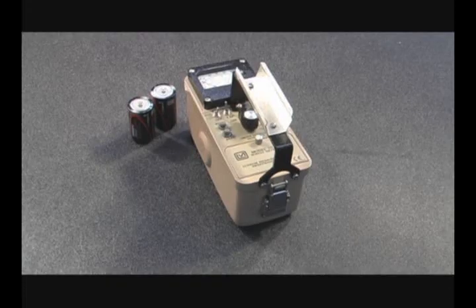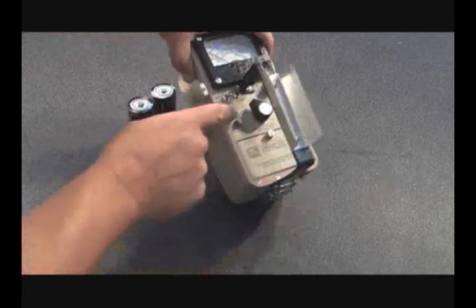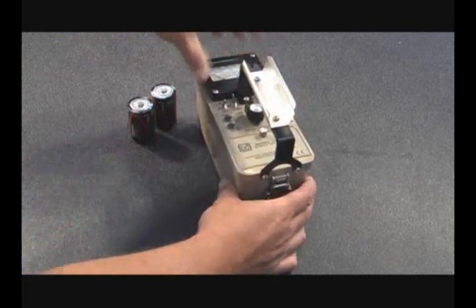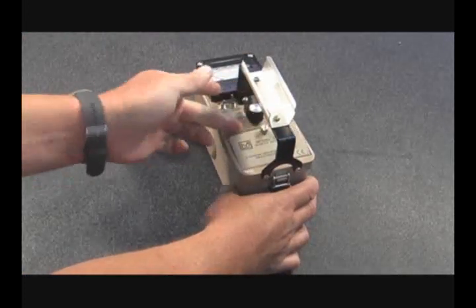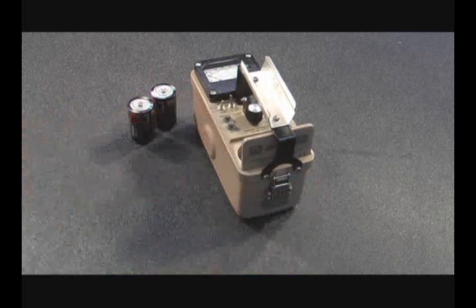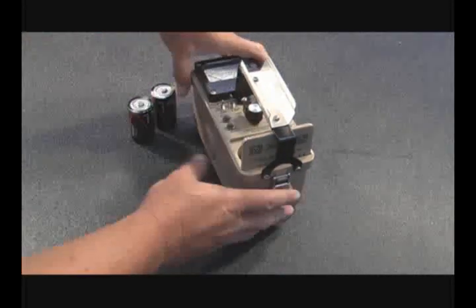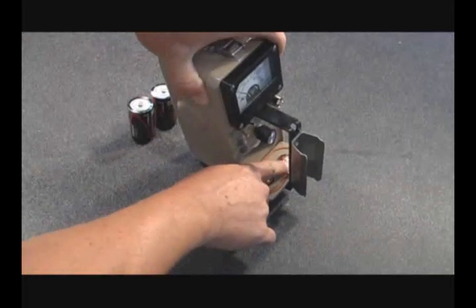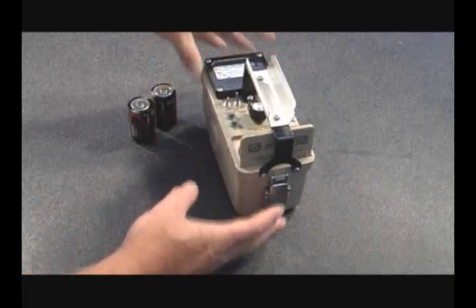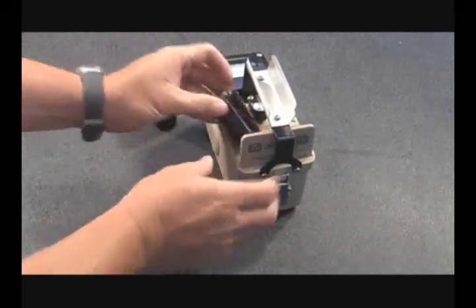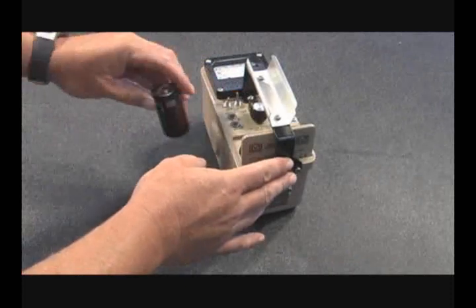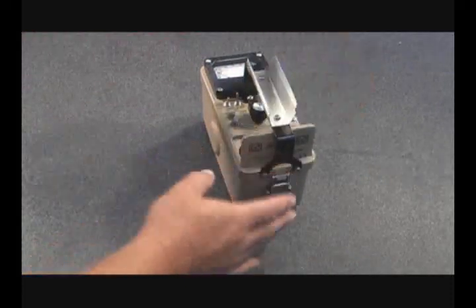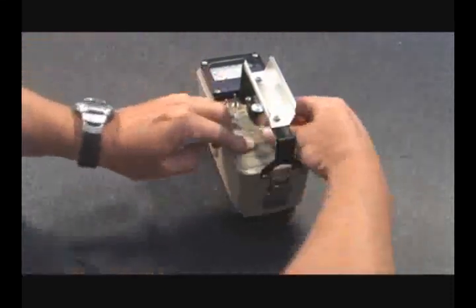To install the battery, first make sure that the range selector switch is in the off position. Open the battery compartment lid by pushing down and turning the thumb screw 1/4 turn counterclockwise. Note the negative and positive marks on the inside of the lid. Install the batteries matching the battery polarity with these marks. Reversing the battery polarity will not harm the instrument, but it will prevent it from functioning. Close the battery compartment lid.